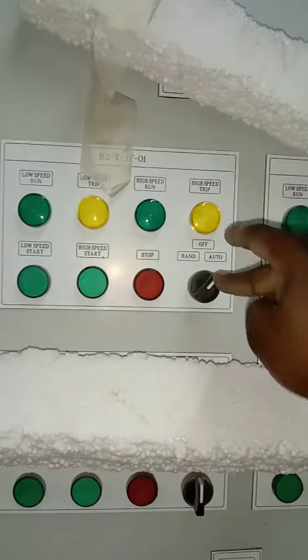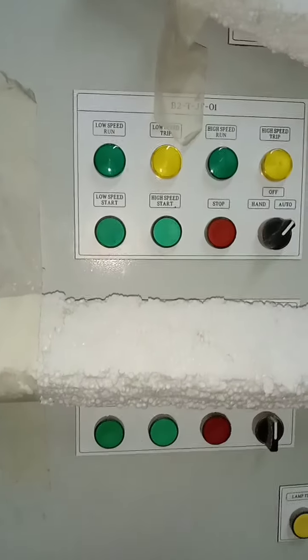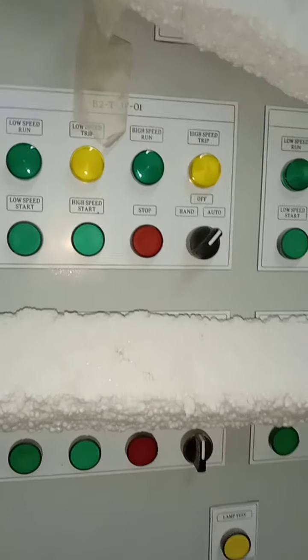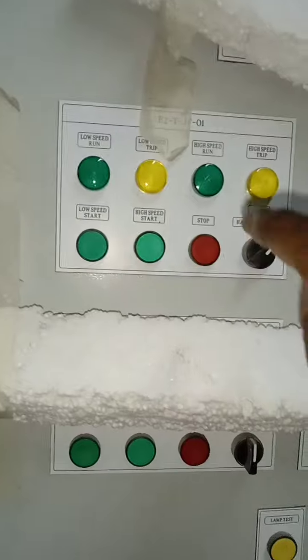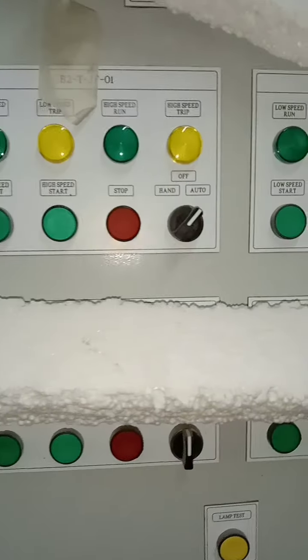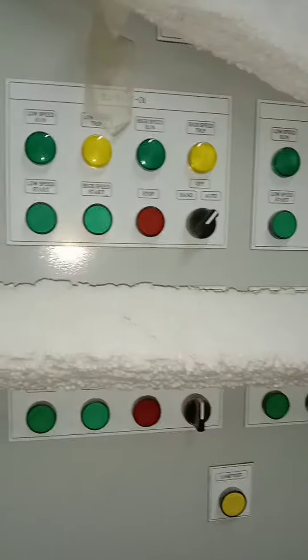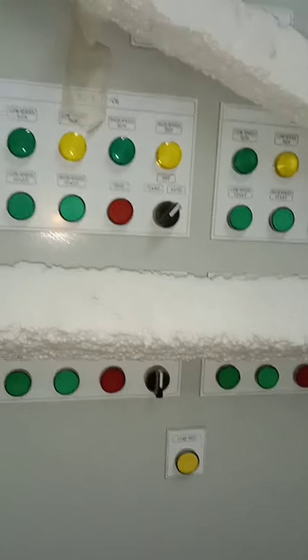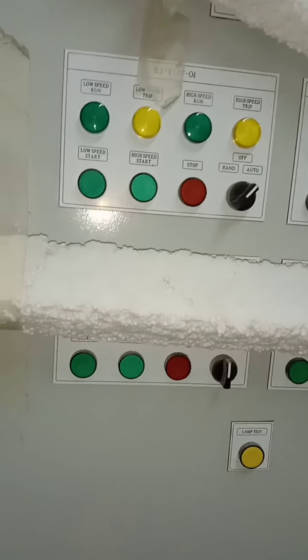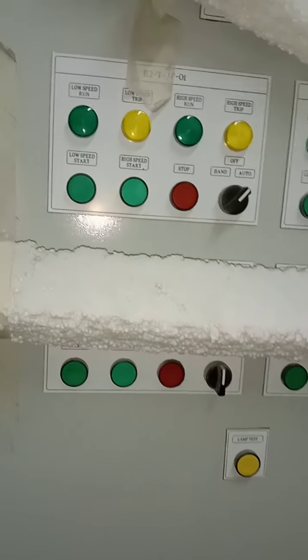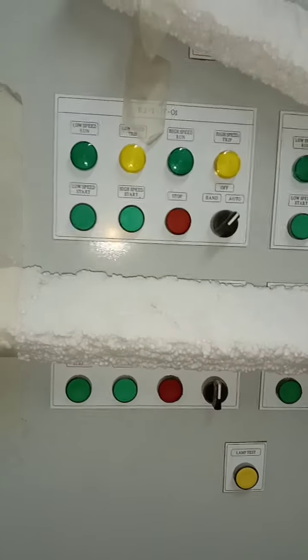If I turn to auto, it means the fan will operate automatically by the help of BMS or through the fire alarm system. We'll have third-party cables that are leaving from a relay control module in order to give supply to the fans for it to function in automatic condition. In the case of BMS, it will be operated from the BMS control room. And in the case of fire alarm system, it will be operated from the fire alarm control center, or probably by the use of the relay module like I mentioned. The third-party cable is going to drop inside the panel, which I will explain.